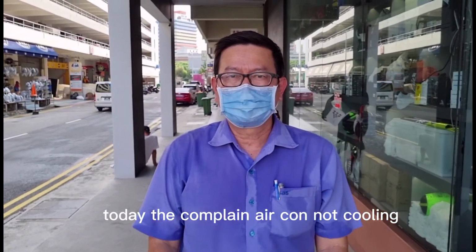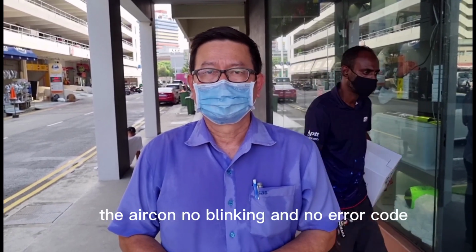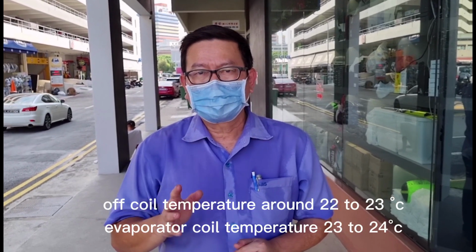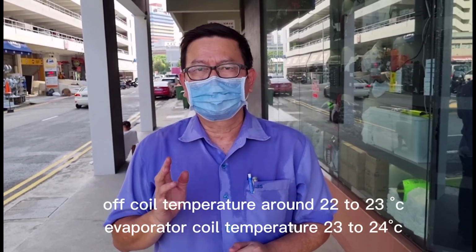Today we got one complaint: the aircon is not cold, the aircon is not blinking, no error code. Off coil temperature is around 22 to 23 degrees. Coil temperature is around 23 to 24 degrees.